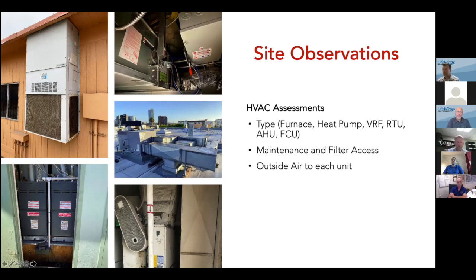The bottom right photo just shows the age of the unit; some of these units are 30 and 40 years old, which makes a difference in how they can perform. The middle photo on the right shows the amount of ductwork on a roof. Ductwork on a roof isn't necessarily bad, but it's susceptible to leaks and growth, and you can see a little moisture sitting on top of the ductwork, which deteriorates rapidly when wet. So that's some of the things we look at. Next slide.